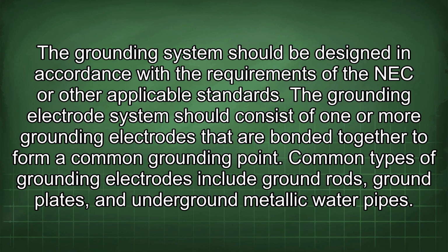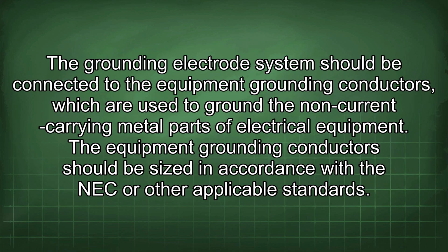The grounding electrode system should consist of one or more grounding electrodes that are bonded together to form a common grounding point. Common types of grounding electrodes include ground rods, ground plates, and underground metallic water pipes. The grounding electrode system should be connected to the equipment grounding conductors, which are used to ground the non-current carrying metal parts of electrical equipment. The equipment grounding conductors should be sized in accordance with the NEC or other applicable standards.